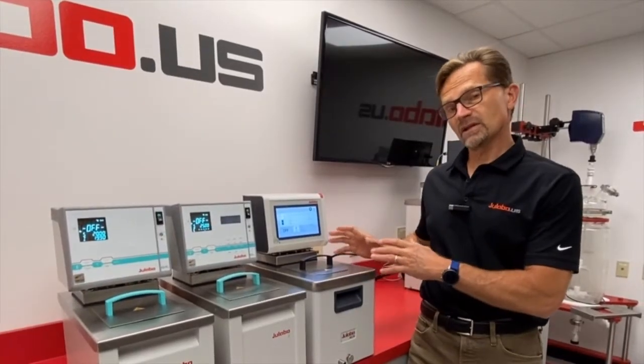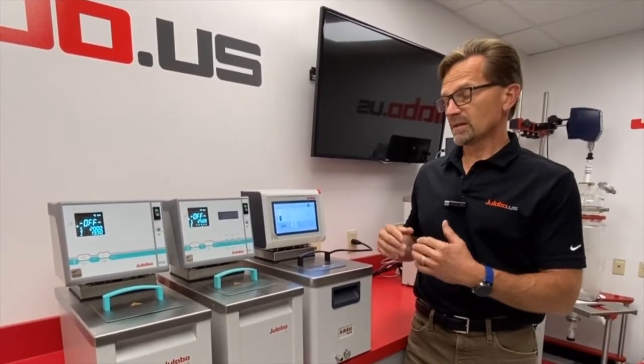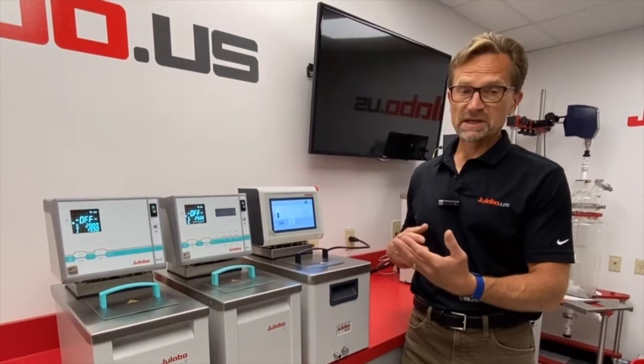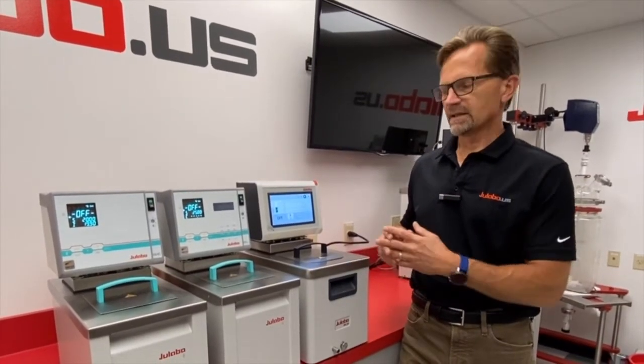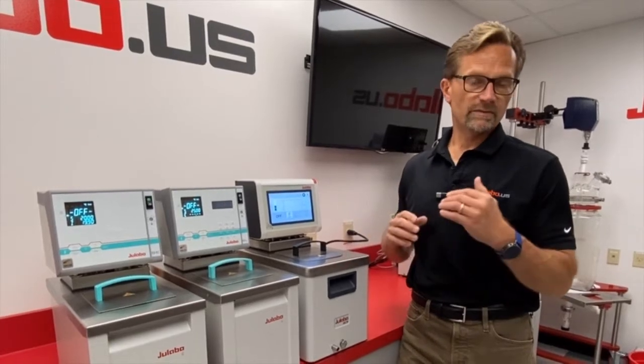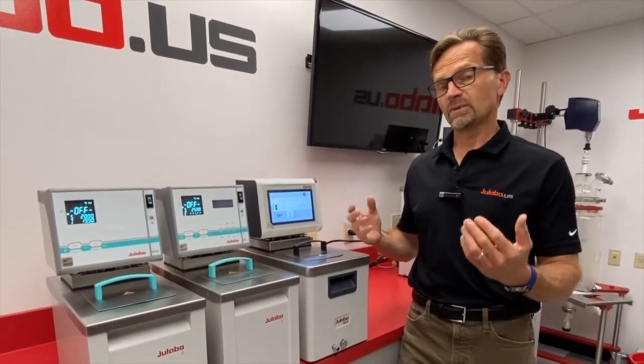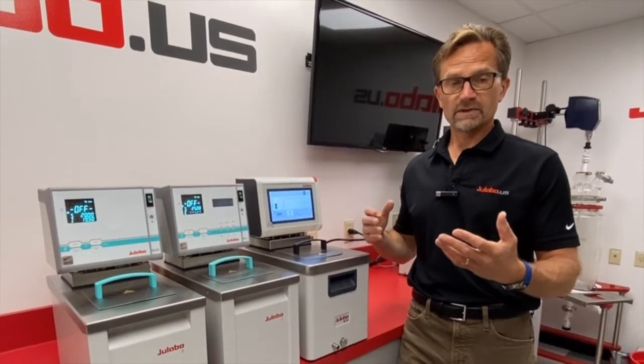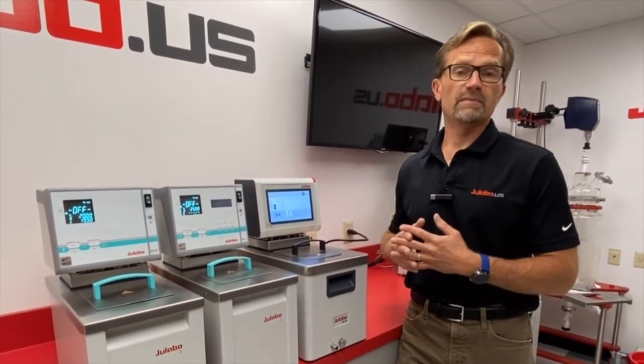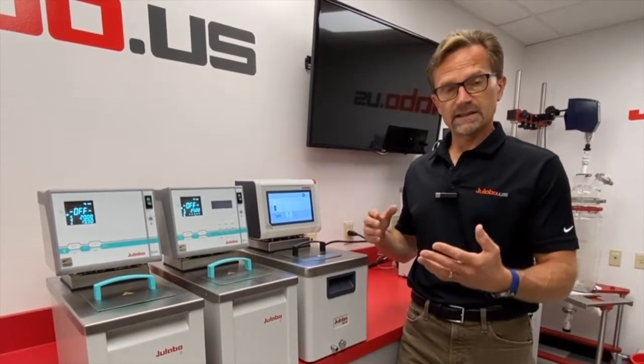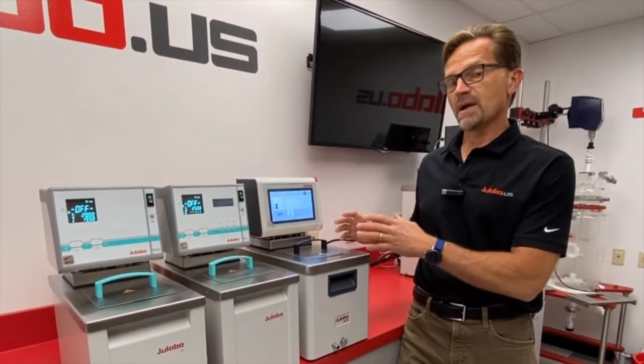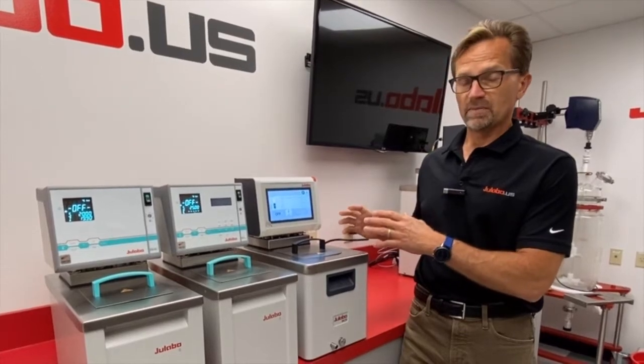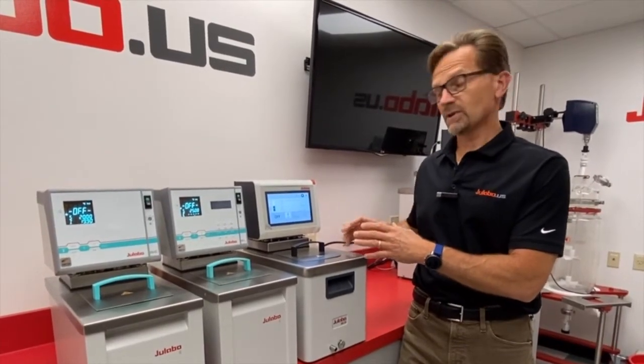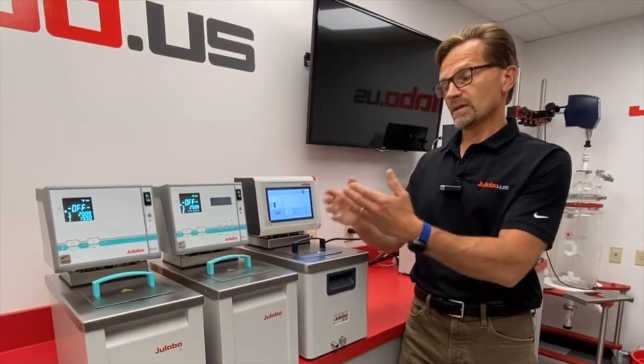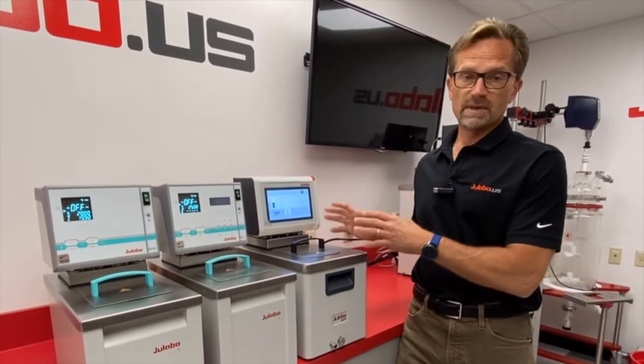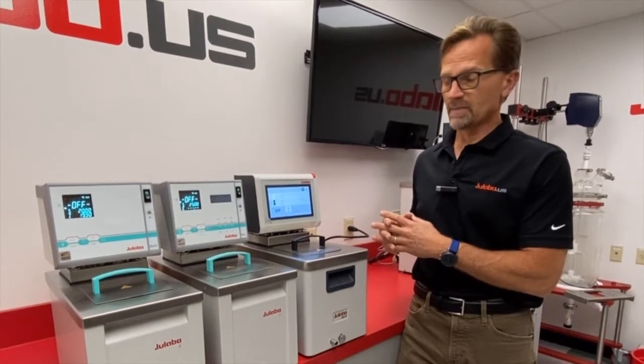The MAGIO MX also incorporates a pressure suction pump, but instead of 4 preset speeds like the SE and the SL have, the MAGIO MX is adjustable from 40 to 100%. So it gives you a broader range of flow rate and pressure. For example, it can do 3.5 to 13.3 psi and 16 to 31 liters per minute. So the MAGIO MX has a higher capability pump from a flow rate perspective. So if you have an application that needs greater flow than what the SE or the SL offer, then you would be well served to choose the MAGIO MX model.